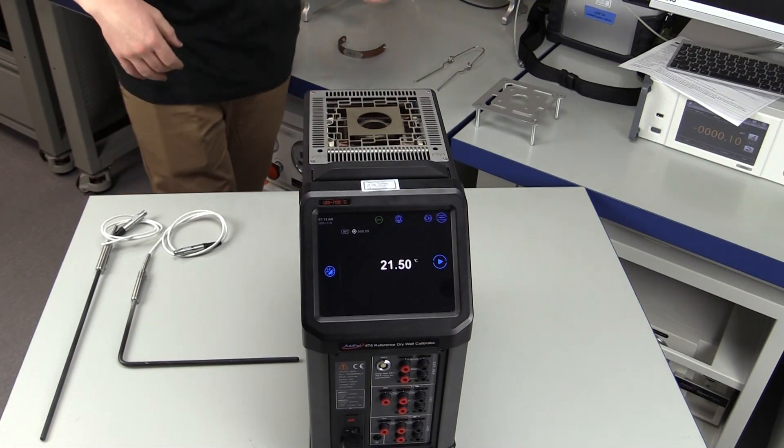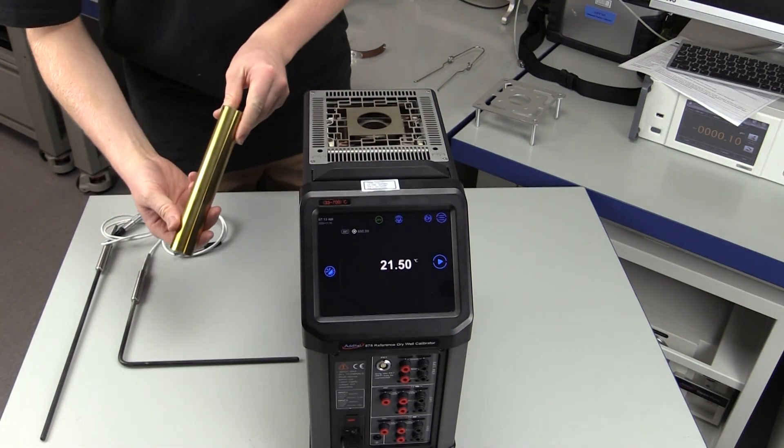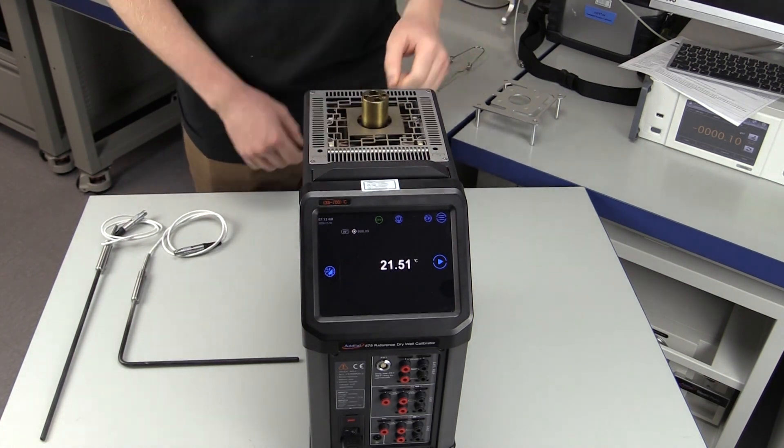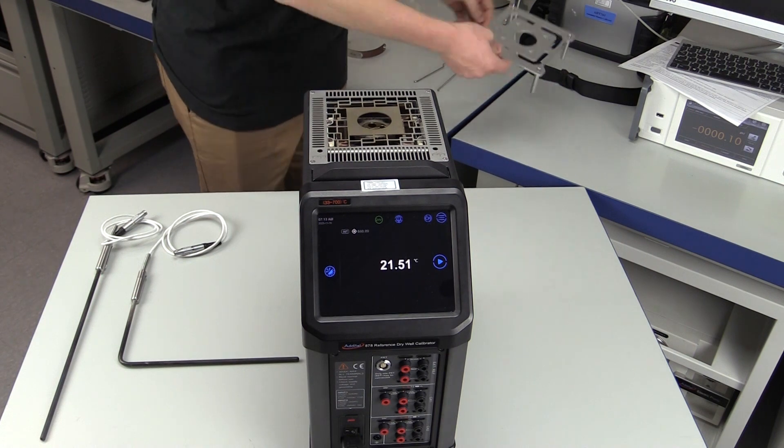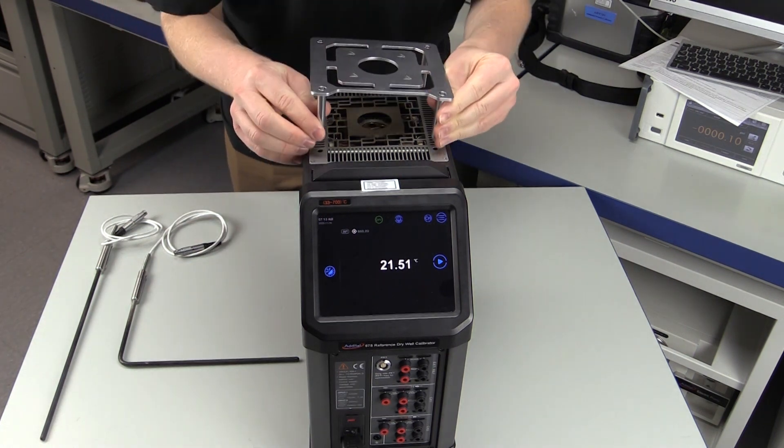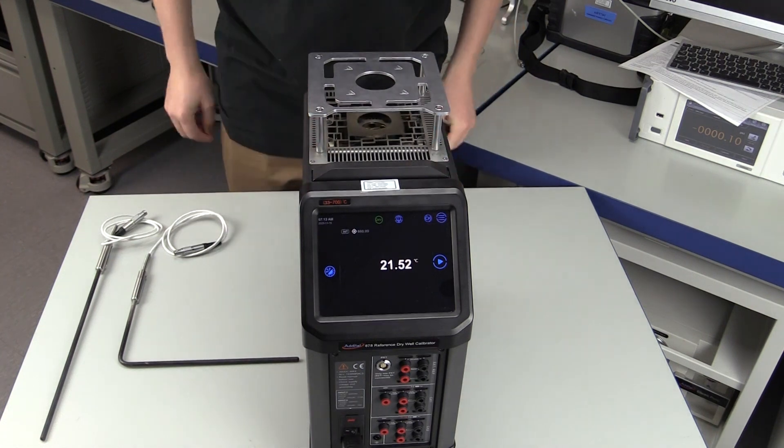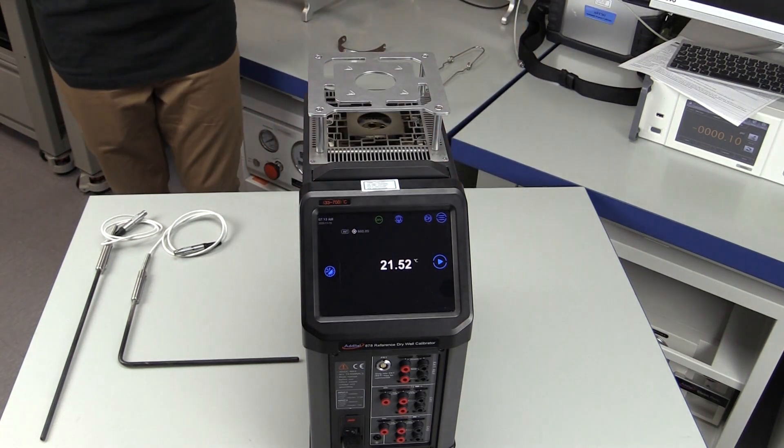We start by carefully inserting the appropriately sized insert into the 878-700 calibrator. Most all of the available Additel inserts have standard hole sizes to accommodate typical PRT dimensions. However, other insert styles are available if needed. Place the accompanying heat shield on the top of the calibrator.